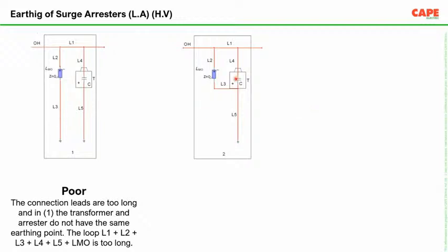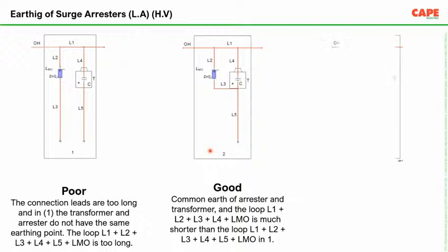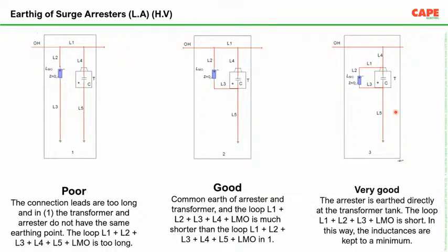The second method recommended in the standard is that the earthing part of the zinc oxide varistor, the surge arrestor, can be connected to the transformer tank. This is an improved way. And the best way of connecting a surge arrestor in the high voltage substation is this way. This is the one which is recommended in the standard.